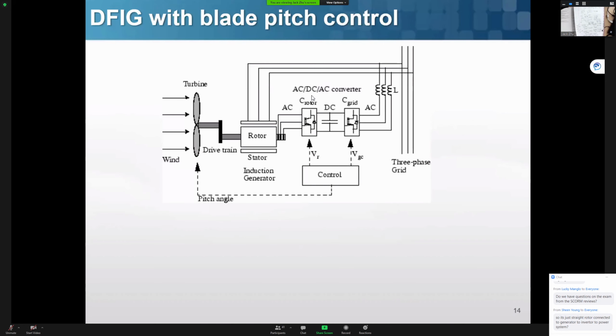So this piece of drawing in your PowerPoint is a doubly-fed induction generator. You will have a connection from the rotor. So your power is generated on the stator. This power is fed to the grid. At the same time, you're going to feed some power back into the rotor. And this control here has some kind of mechanical or electrical monitoring to monitor the speed. They also have to control the pitch angle, and then they will be controlling the firing angle down here. Try to make sure.